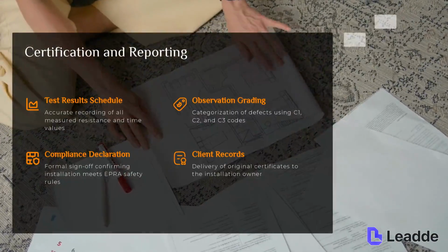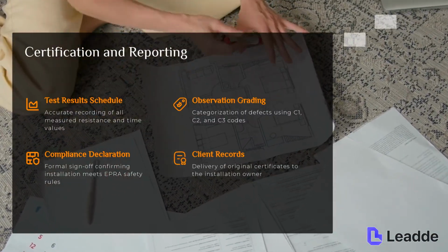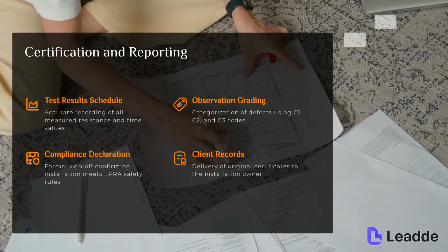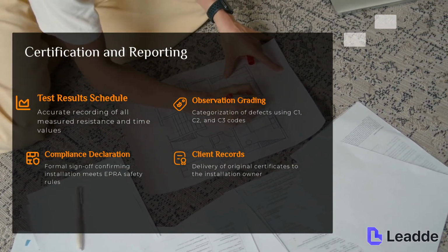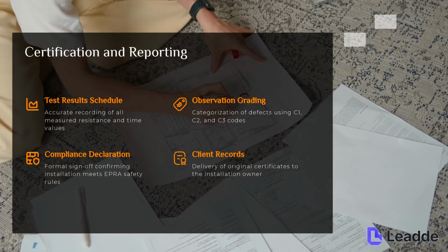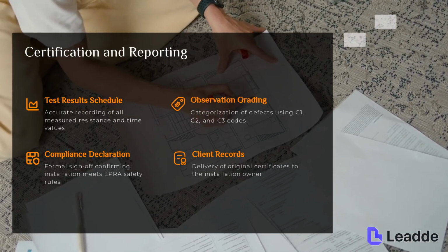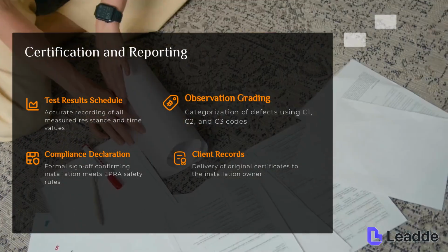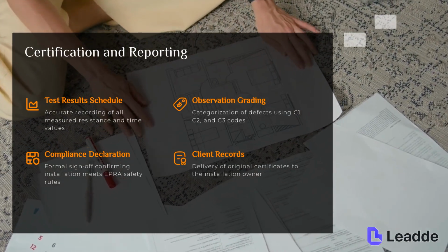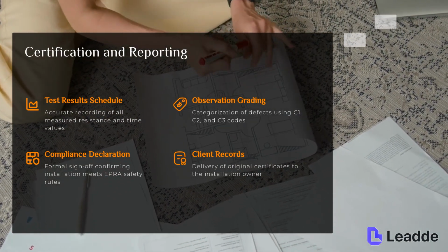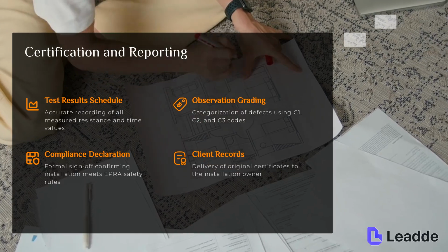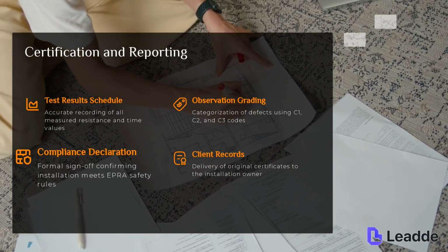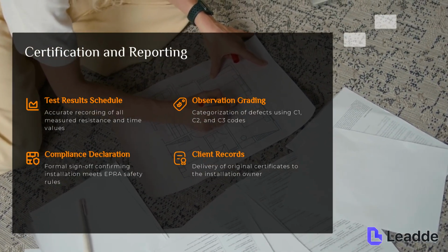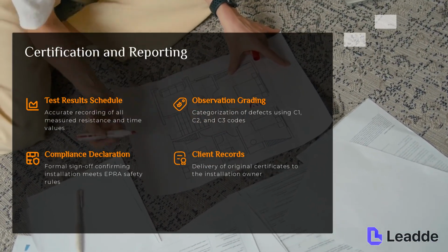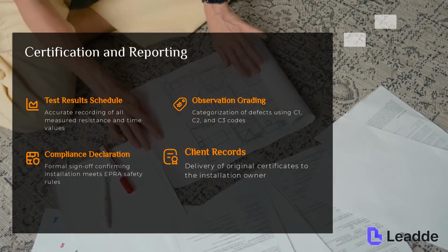The final stage is certification and reporting. A schedule of test results must be completed with accurate recordings of all measured resistance and time values. Any observed defects are to be categorized using C1, C2, and C3 codes. A formal declaration of compliance is then signed, confirming the installation meets EPRA safety rules. Lastly, original certificates must be delivered to the owner of the installation for their records.